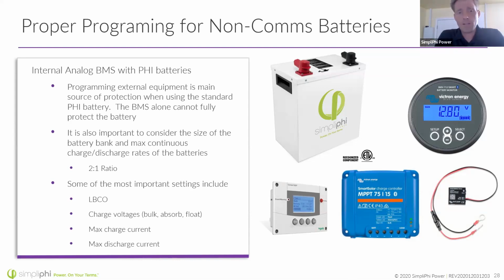So we often recommend, Daniel, 50.1 volts is our 80% depth of discharge. We often recommend that you use 80% as your depth of discharge at 50.1 volts for LBCO. And the reason for that is you get a lot more cycles when you don't cycle your battery all the way down to 0%. Cycle it down to 50.1, you'll get 80% of the available energy out of your battery, but you're going to get 10,000 cycles out of that battery. If you're cycling once every day, that'd be 27 years. It's a very, very long time.